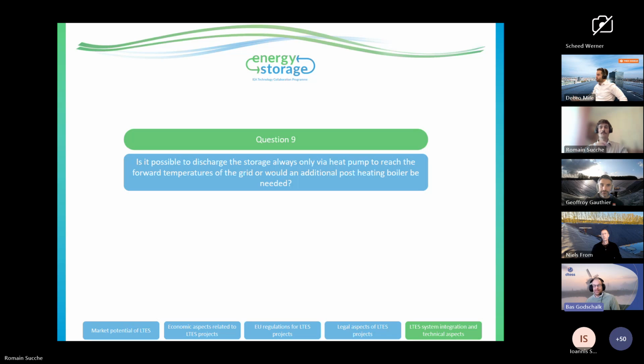Normally, we would recommend that if you can skip the heat pump in your energy concept, that will be much better. You have a smaller investment, but also smaller operational costs. We normally do an assessment when there is a question from a client to see what is exactly the total ecosystem of the heat needed, which can be stored, and then see if a heat pump is needed or not. And in some cases, it's more efficient to run everything at a lower temperature without a heat pump. But if you need it, then you need to add it to your energy concept. So I don't think there's one clear answer. It always depends on the situation, and you have to evaluate and calculate what is the most optimal solution. And then it depends on whether you want to focus on the capex, on the operational cost, on the sustainability, etc.